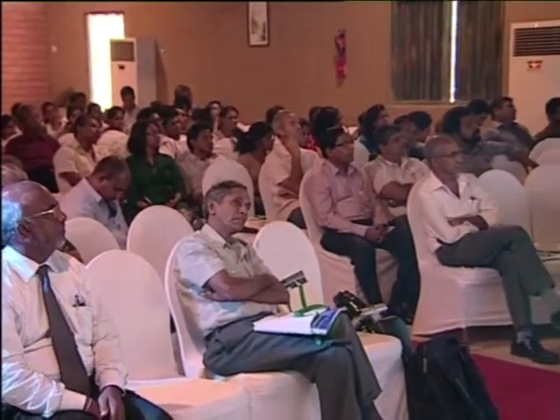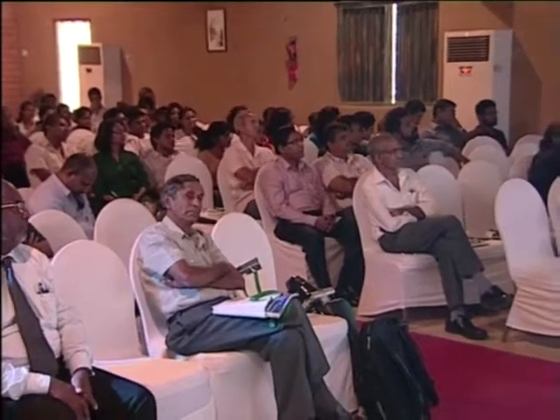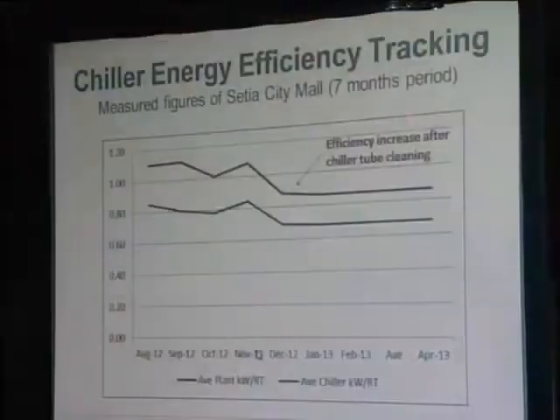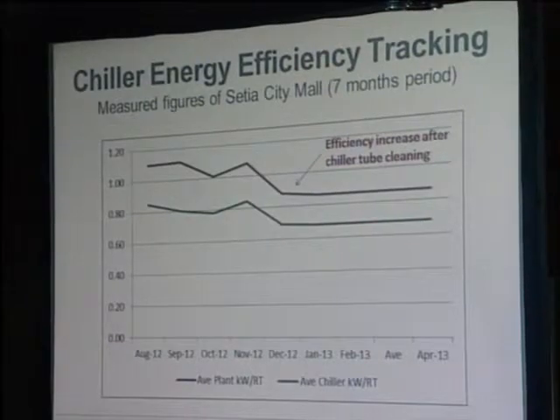We did some energy efficiency tracking as part of the energy management system, and you'll notice that the efficiency of the chiller improved by reducing the kilowatts per refrigerant ton. That was simply because we realized through all these works the chiller had gotten dirty. So by cleaning the chiller tubes, that helped greatly. In our projects now, often we'll install this kind of automatic chiller tube cleaning system, so you make sure it stays clean.